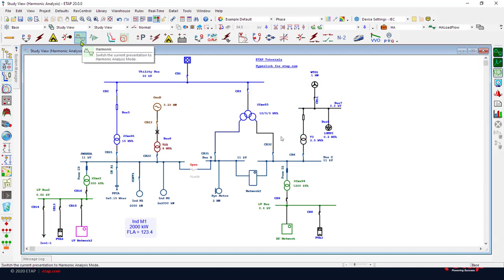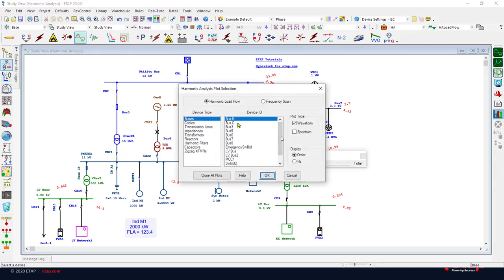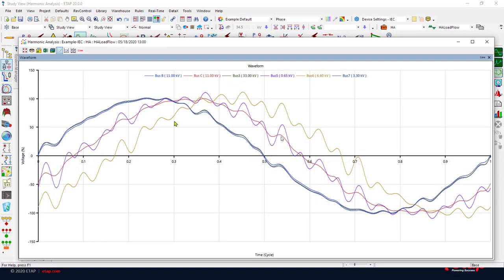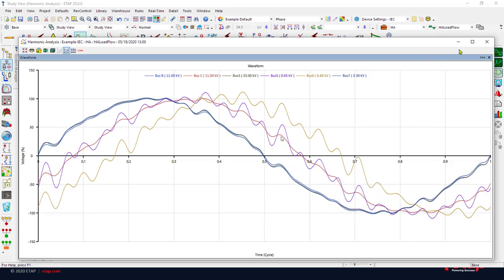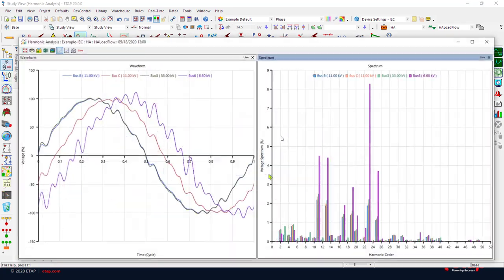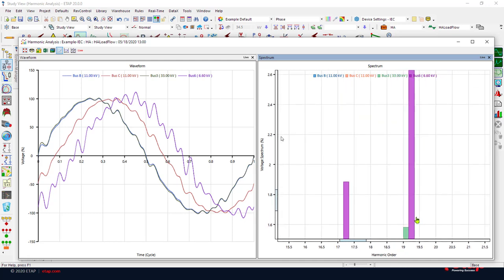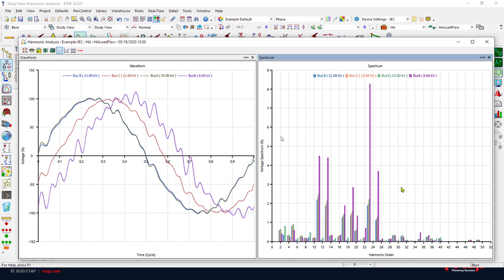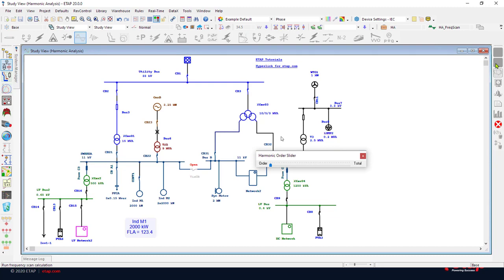Let's take a look at the PlotView visualization for harmonics in action. With our example file, we run our harmonic simulation, go to our plot selection page, select the buses to plot, select the plot type, and click OK to get the visualization of the waveforms. The hairline gives us information for every single chart. Going back to plot selection, we can select multiple buses and bring up waveform and spectrum — the line charts and bar charts have both been changed into nice colorful charts that you can customize for your study deliverables. You can also use these charts for frequency scan, simply opening the plot selection and plotting the impedance magnitude.